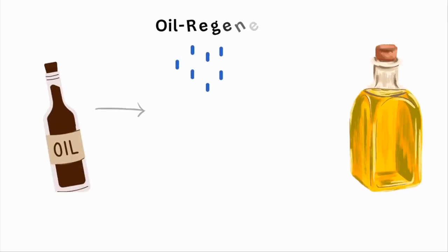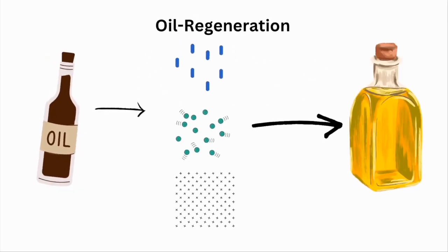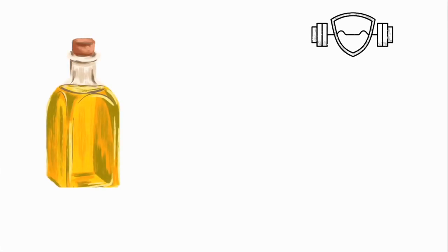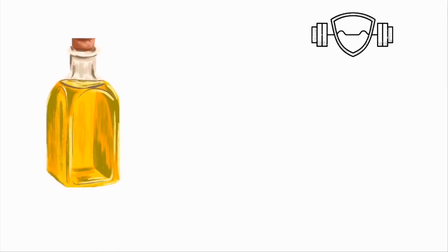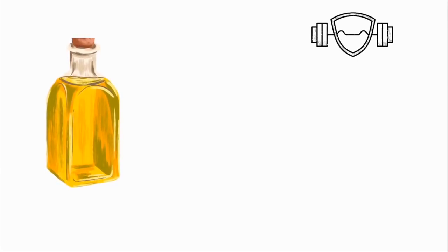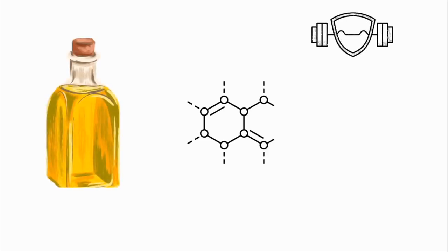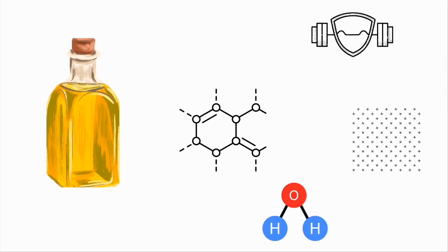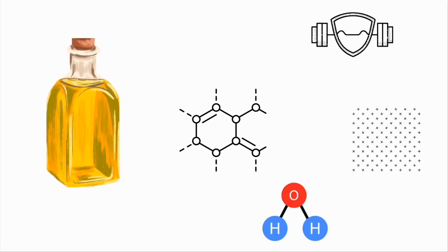It does the removal of dissolved gases, it does the dehydration, and it restores the properties of the oil, right? That's when we talk about our dielectric strength, also called the breakdown voltage that I was mentioning prior, and the acidity and the hydrogen and all other properties in the oil of a transformer, they are also improved.